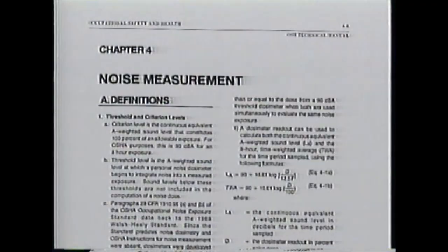The dosimeter is our primary compliance instrument. So don't forget about the Field Operations Manual guidance for policy and your OSHA Technical Manual Chapter 4, Noise Measurement, when it comes to the dosimetry aspects. What we're covering here are the Type 2 sound level meter, which would be used for screening survey purposes, referral purposes, and perhaps on occasion backup readings.